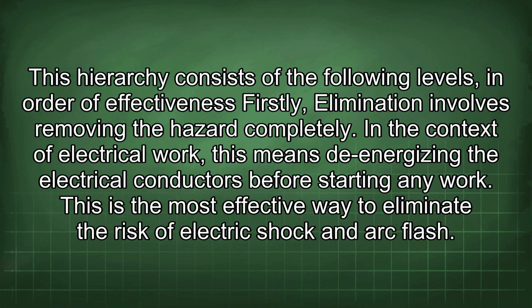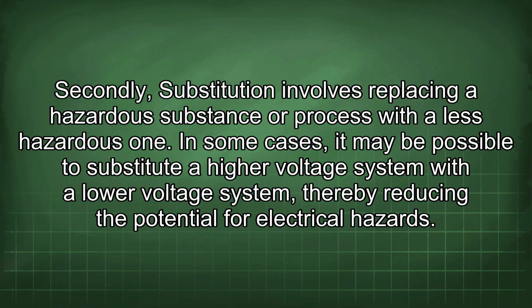In the context of electrical work, this means de-energizing the electrical conductors before starting any work. This is the most effective way to eliminate the risk of electric shock and arc flash. Secondly, substitution involves replacing a hazardous substance or process with a less hazardous one. In some cases, it may be possible to substitute a high voltage system with a lower voltage system, thereby reducing the potential for electrical hazards.